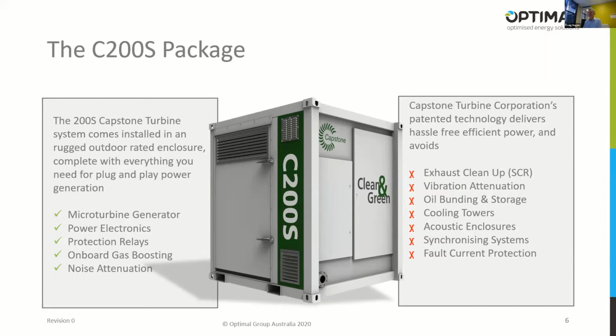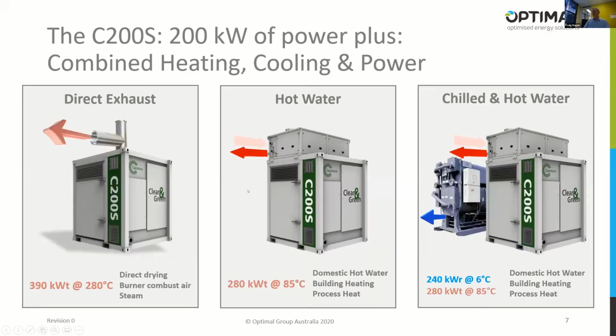The bearings are basically a non-serviceable item. Every 40,000 hours, which is about 4 years of operation, we come and change the power head. The old power head goes back to the United States and is remanufactured, and we give you a new one. So you're not changing lube oils, bearings, spark plugs, and all those things we'd be used to on conventional combustion engines.